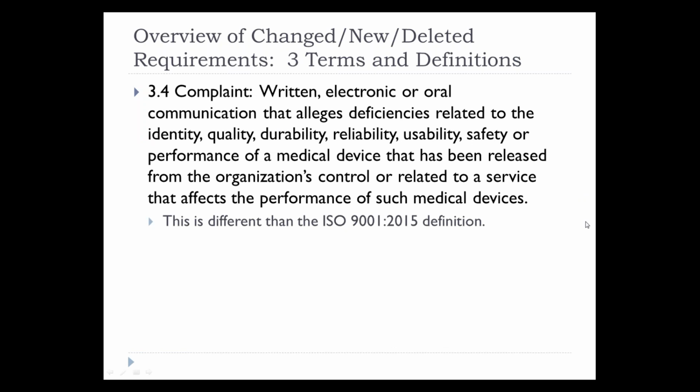Section 3.4, complaint. I've chosen to focus on this definition because the 13485:2016 definition of complaint is different than the 9001 definition of a complaint. And it's the written, electronic, or oral communication that alleges deficiencies related to the identity, quality, durability, reliability, usability, safety, or performance of a medical device that has been released from the organization's control, or related to a service that affects the performance of such medical devices. So again, a very specific definition related to 13485:2016.